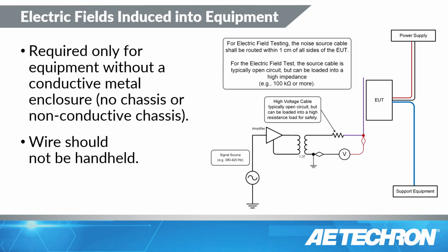Now, for the electric field induced in the equipment, you're going to be placing 170 volts on that wire. And so what I recommend doing is using that T3700 step-up transformer and a safety resistor. It's not required, but it's really a good idea to have one there. And that safety resistor is going to be some type of high voltage resistor, and usually a high value as well, say like a 100K ohm resistor. Here's why. Since I have an open-ended wire here, if there's any exposed metal at the end of that wire and it touches ground, you could potentially short this thing to ground, which might cause some excitement, and we don't want that.